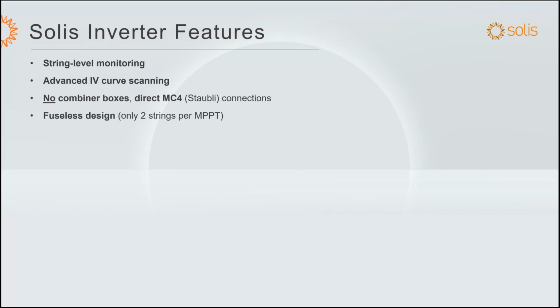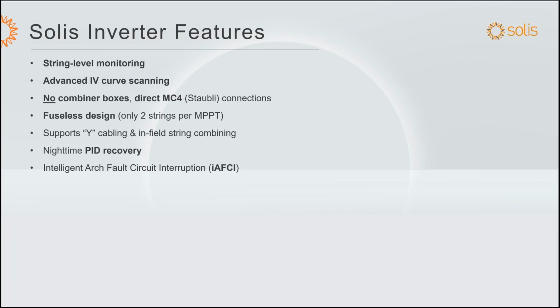They are fuseless designs, so all of our inverters have 2 strings per MPPT, and because of that, you do not need fuses, which are another potential failure point. As we saw on the previous slide, you can support Y cabling if you want to do in-field string combining. We have nighttime PID recovery for those that are experiencing issues with modules and PID. We also have intelligent AFCI on all of the inverters, and you could isolate the MPPT if needed of the inverters that are having issues. We have type 2 surge protection on both the AC and the DC.